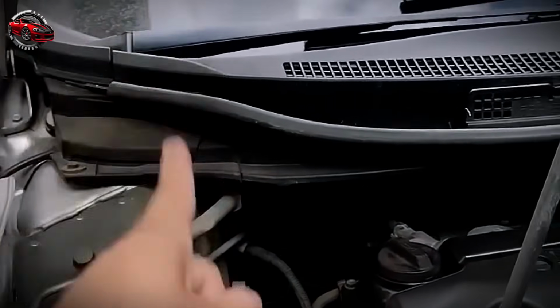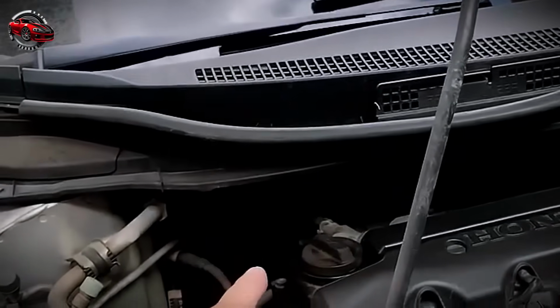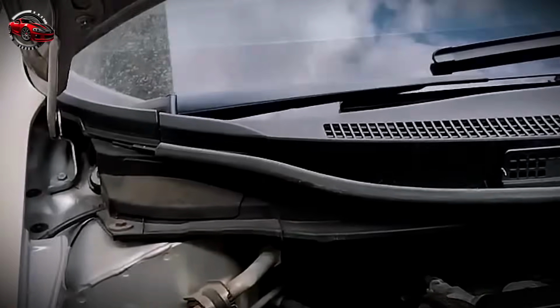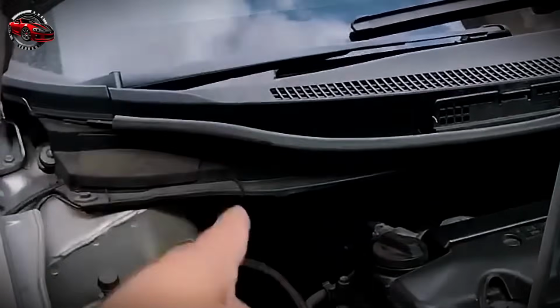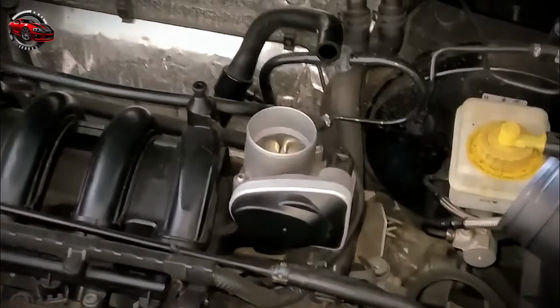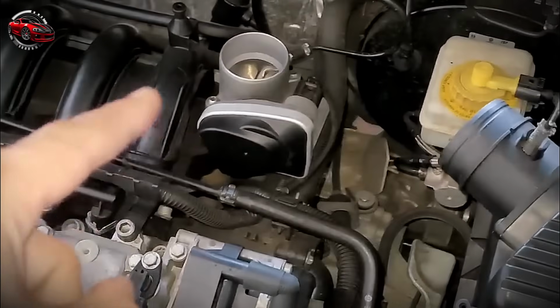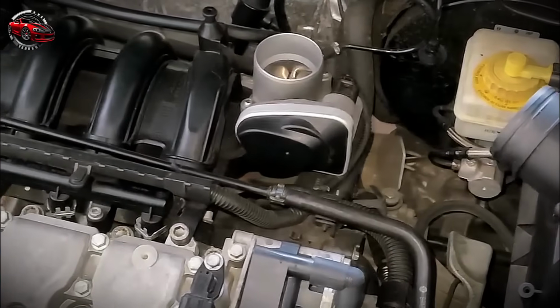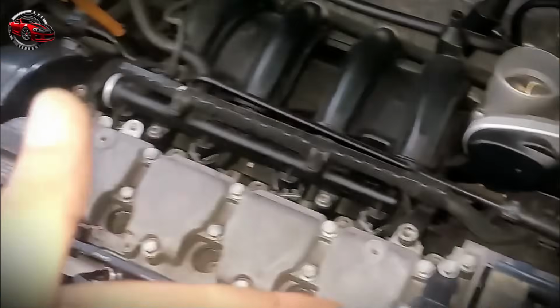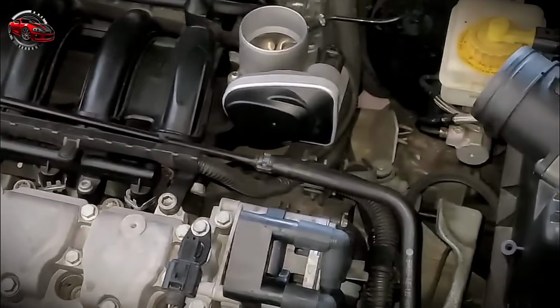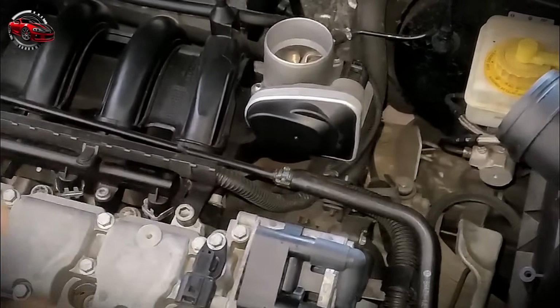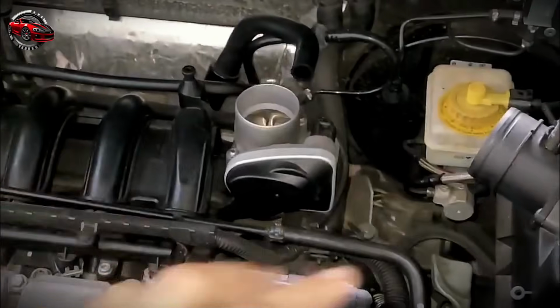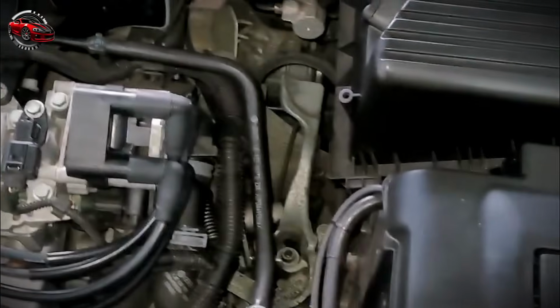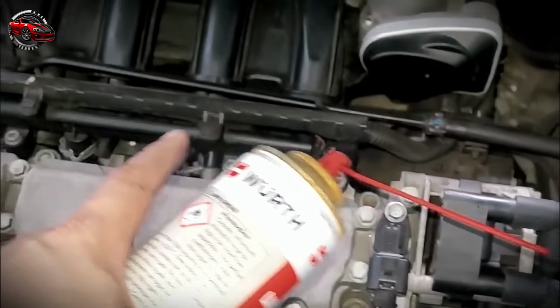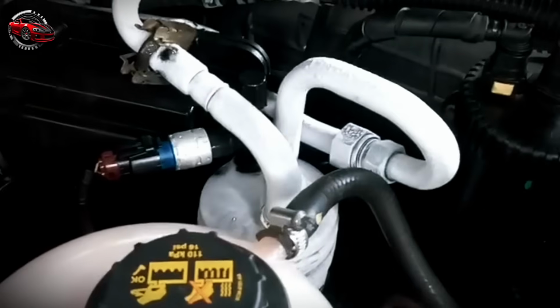It is absorbing all that radiant heat. Every degree of heat that pipe absorbs is a degree of cold that doesn't make it to your vents. It's simple thermodynamics. This heat absorption forces the compressor to work harder to get the refrigerant cold again. It's a quiet, parasitic loss that robs your system of 3, 5, even 7 degrees of cooling power. The fix is almost too simple. Think of it like putting a koozie on your system. You're going to insulate that line.